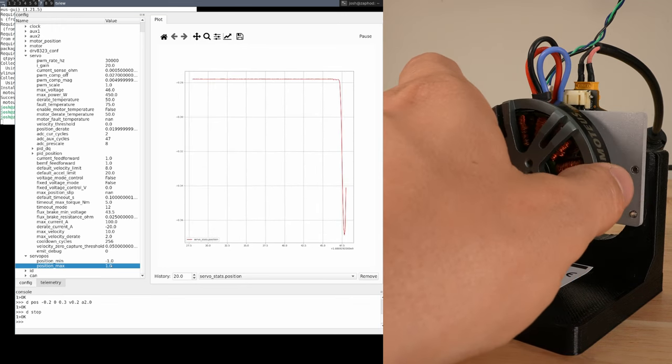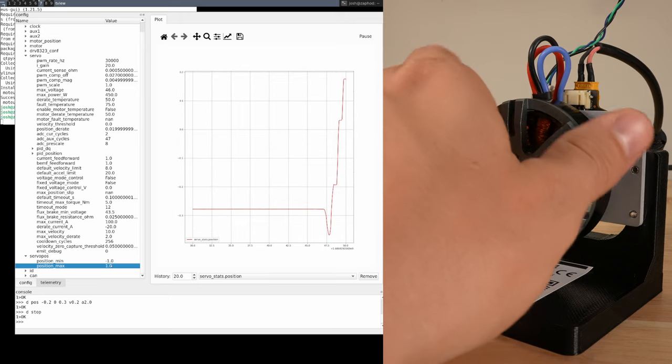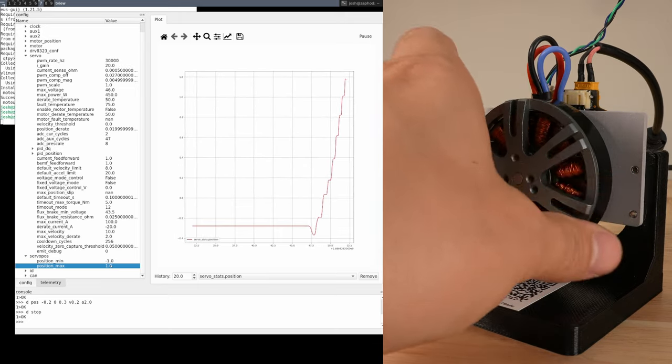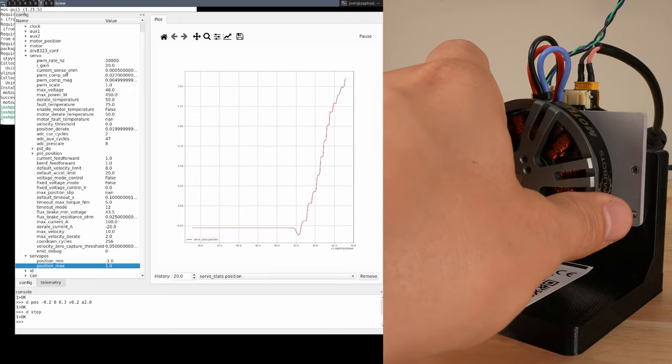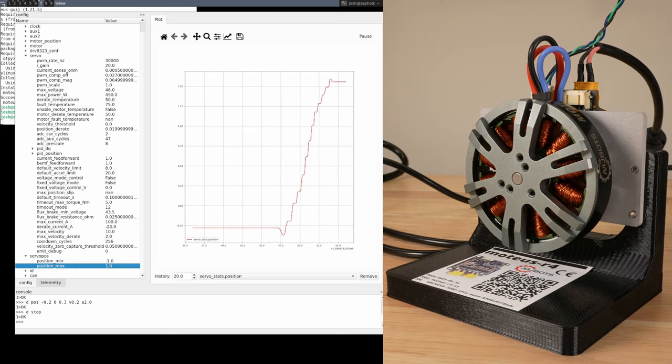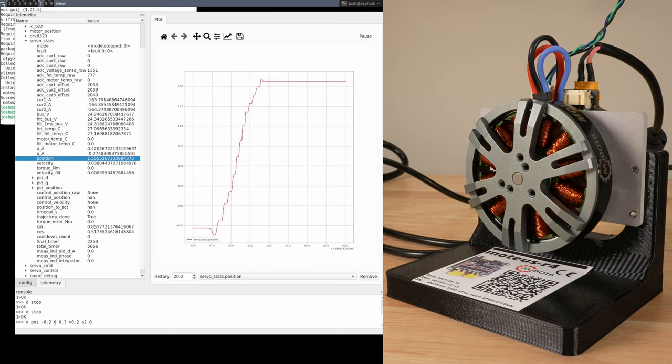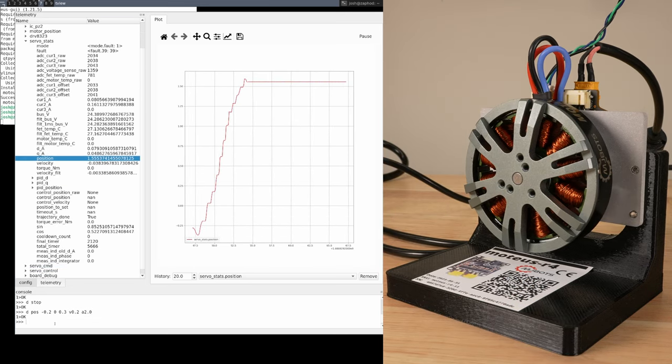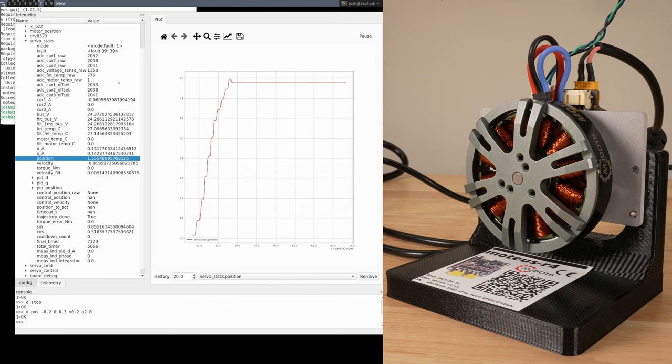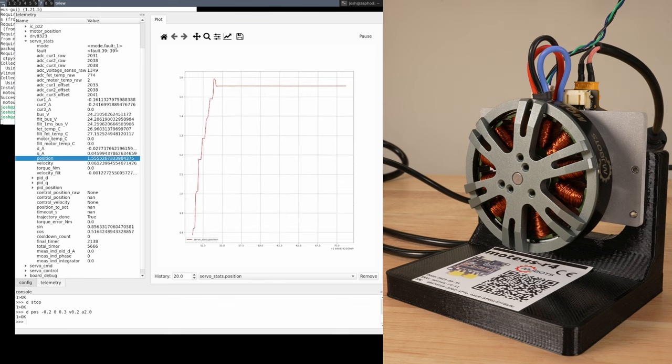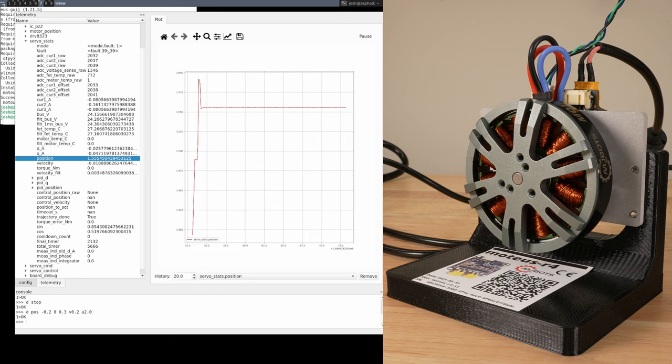if we manually move the motor to plus 1.5, then try the d pos command we issued earlier, we see that the motor doesn't move, and the mode is now kfault, and the fault code is 39.